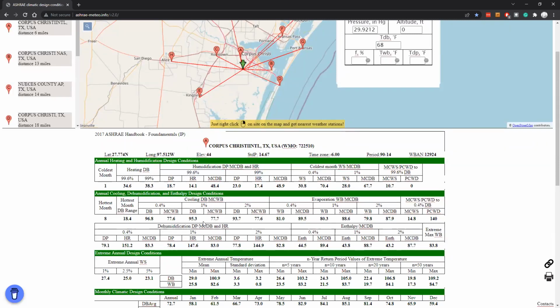On the dehumidification side, your peak dehumidification day—I don't know who makes these rules, but it's the 0.4% day that you use for peak dehumidification. My dew point is 79.1 degrees, by the way, so anything colder than 79 degrees causes condensation. That's a big deal.